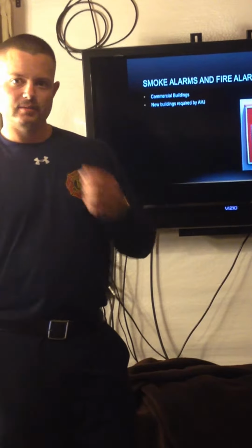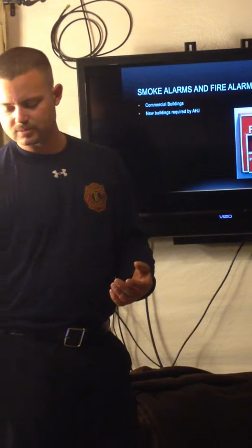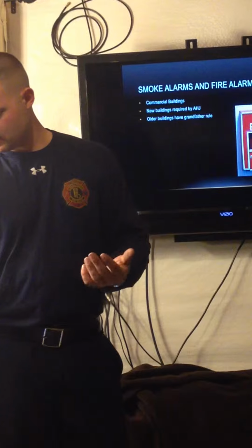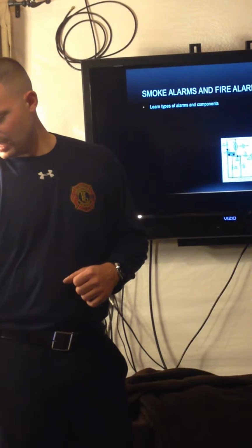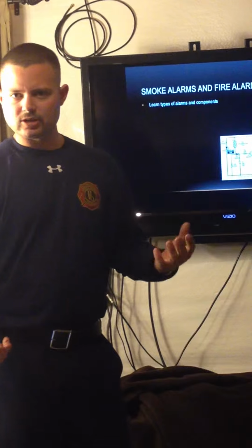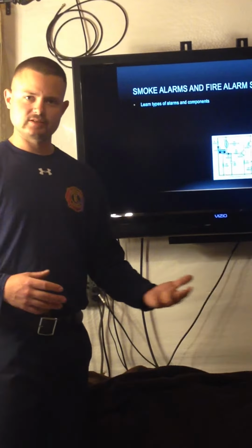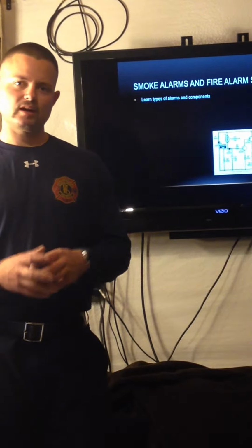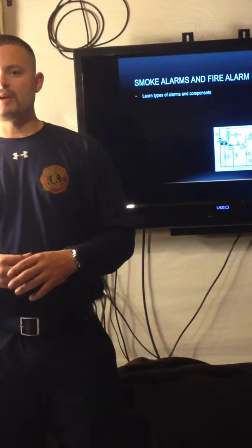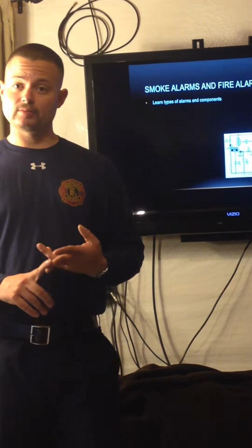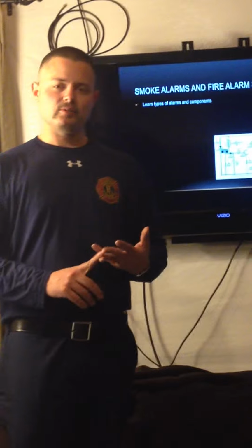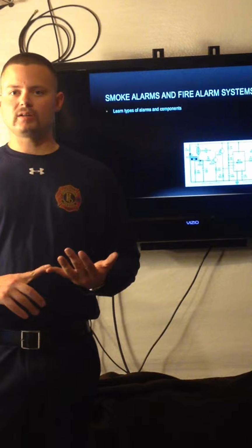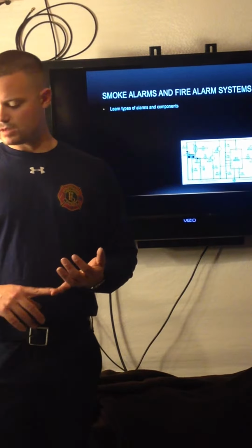New buildings are required by the authority having jurisdiction to have fire alarm systems, usually by the IFC of whichever year they're using. Older buildings are grandfathered in. We always want to try to learn the components and the types of smoke detectors and alarm panels and systems we have in a building. There are multiple manufacturers within our fire protection world of alarm systems, so we have to be familiar with how to properly silence them, how to get a good reset, and understand how we detect which detector was activated, and we can read which zone and be able to read a map on our schematics to know where that activated head is.